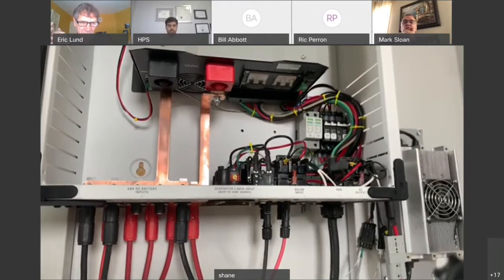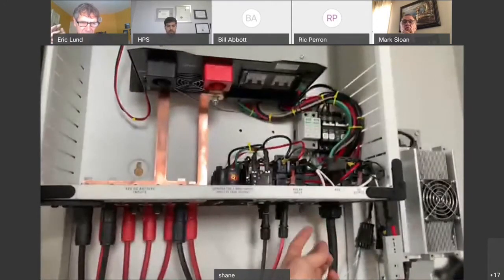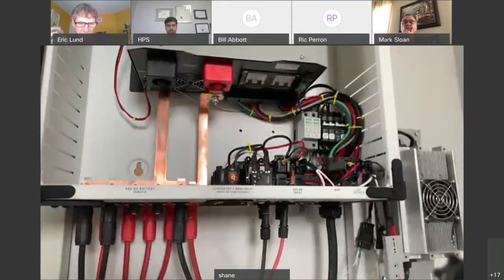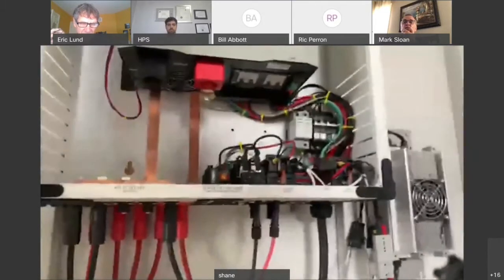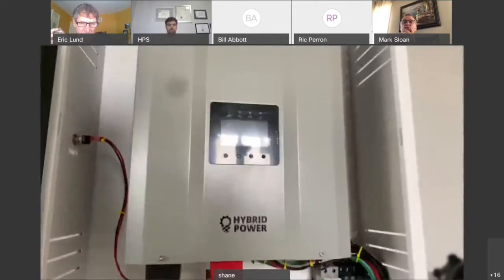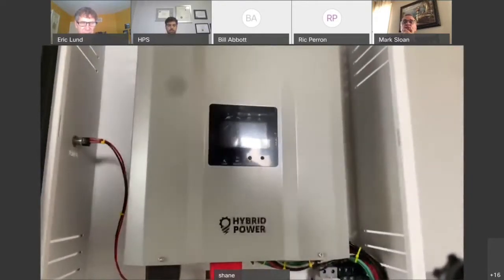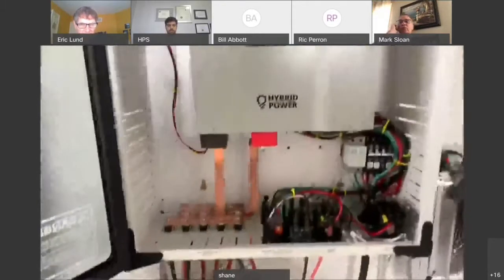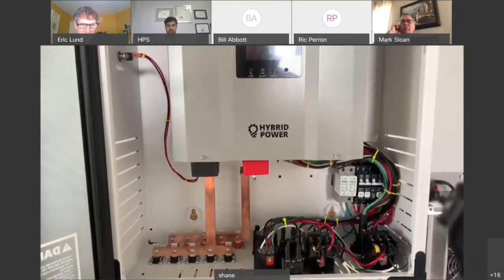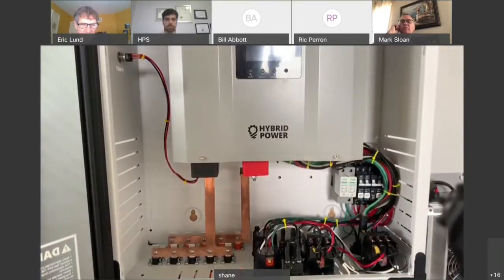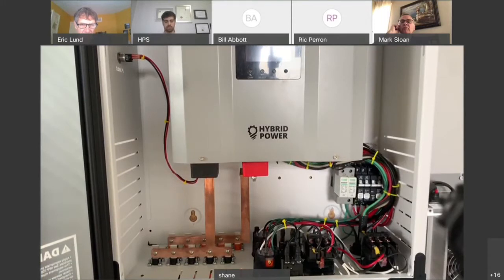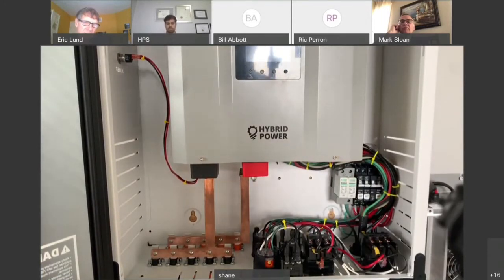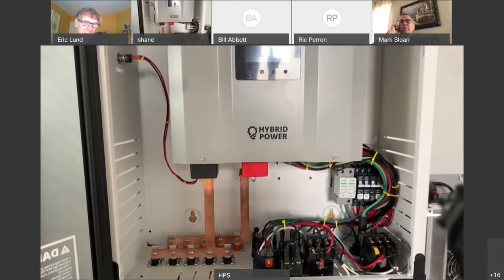Also down here, we have our AGS input, which is just an automotive 2-pin connector. The way the AGS works is on the batteries. If they go down to a certain level, that contact will close and stay closed until it reaches its desired voltage level. The AGS should have a time delay on it, and I believe the new firmware is going to have that, so it gives the proper generator warm-up time. Yeah, that's going to be a 60-second delay.